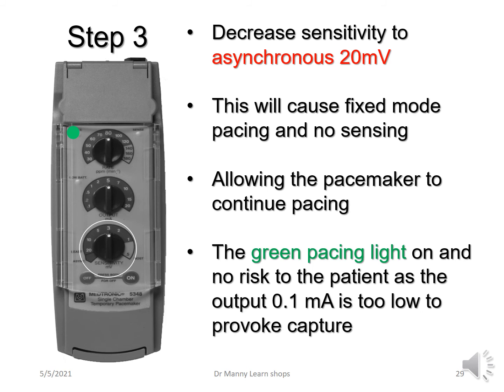In step three, you decrease the sensitivity — the third dial — turning it all the way around to asynchronous, past 20 millivolts. This causes fixed mode pacing with no sensing, allowing the pacemaker to pace continually. You're not concerned about asynchronous pacing because the patient is in their inherent rhythm. The green pacing light will still flash because the output is at 0.1 milliamp — too low to provoke capture of the myocardium — but pacing will continue.